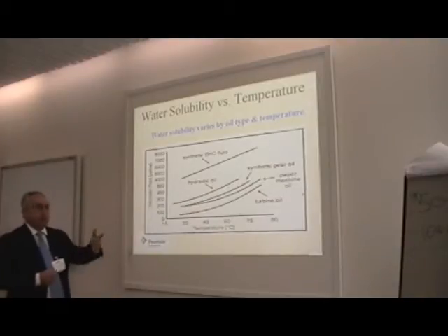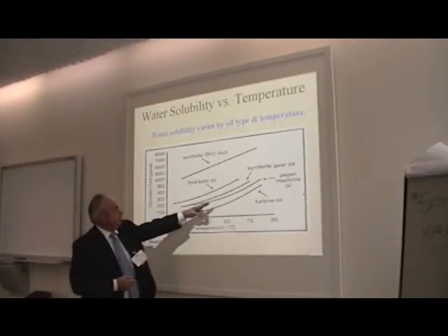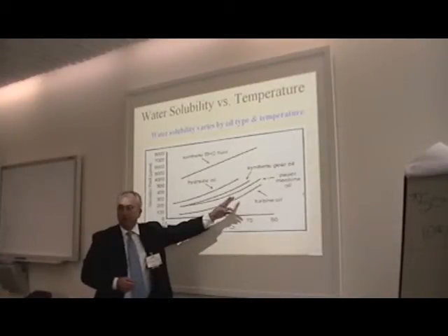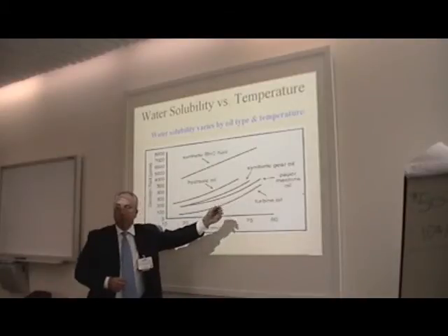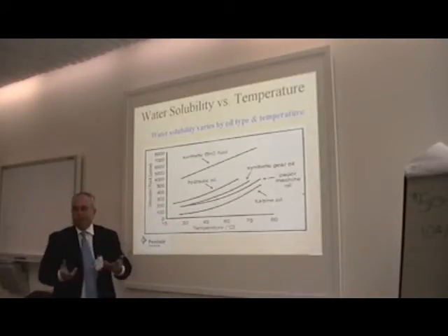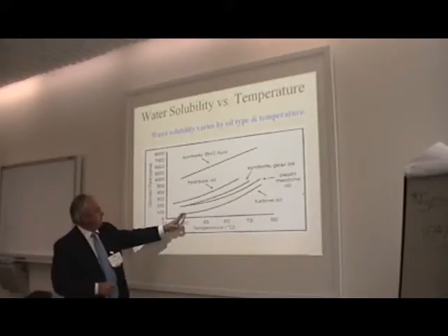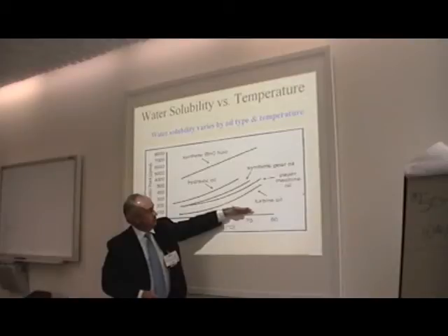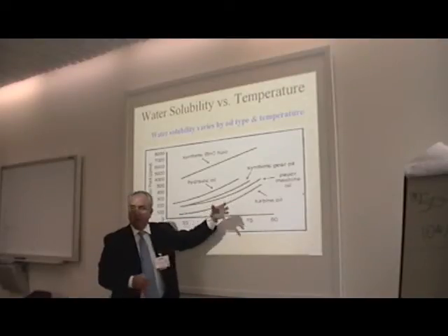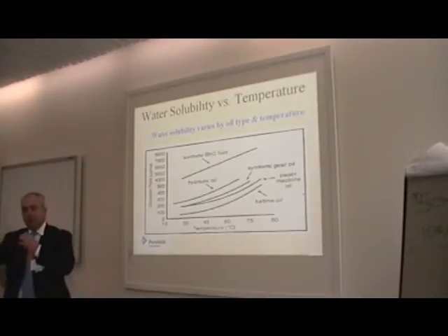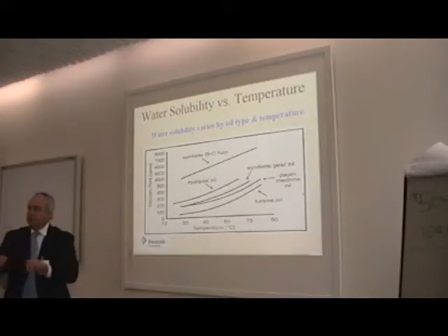In the example she had, they took an oil that was at about 250 ppm on a turbine oil. That's right around your operating saturation level. By cutting it to 40 ppm, which is a quarter of its saturation level, 20% saturation, all of a sudden you've got this huge cushion in the oil. You've got all this space that's available for discrete moisture that comes in. Because moisture is going to come in. These machines heat up, they cool down, they breathe. They're a very humid environment typically, so they're going to pull moisture in. So the key with the technology is getting it out.